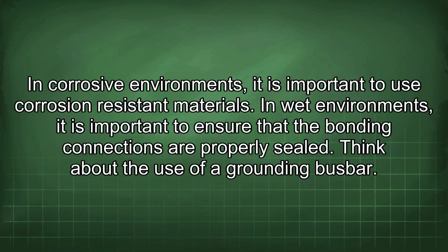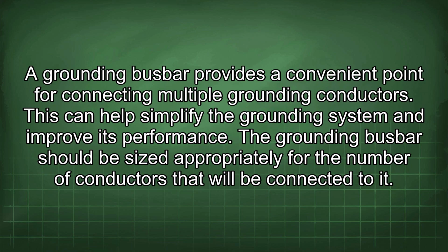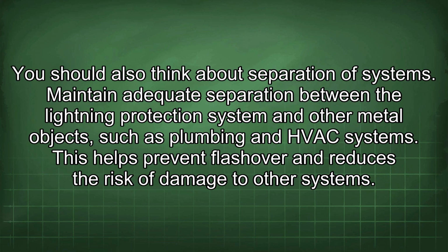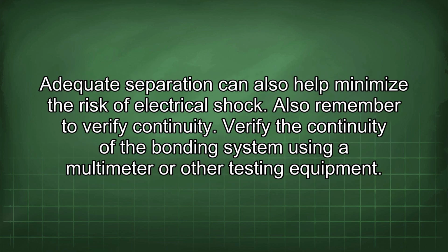Think about the use of a grounding busbar. A grounding busbar provides a convenient point for connecting multiple grounding conductors. This can help simplify the grounding system and improve its performance. The grounding busbar should be sized appropriately for the number of conductors that will be connected to it. You should also think about separation of systems. Maintain adequate separation between the lightning protection system and other metal objects such as plumbing and HVAC systems. This helps prevent flashover and reduces the risk of damage to other systems. Adequate separation can also help minimize the risk of electrical shock.